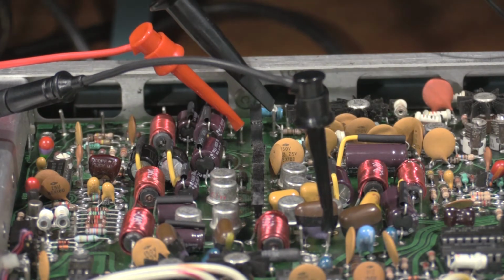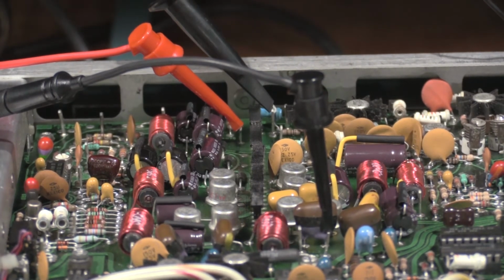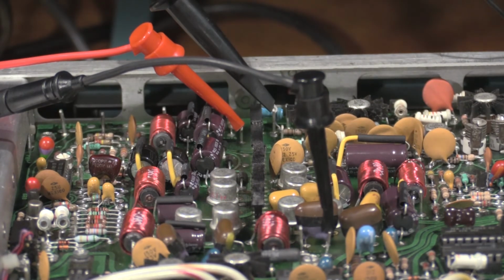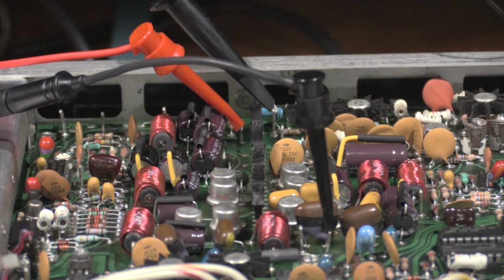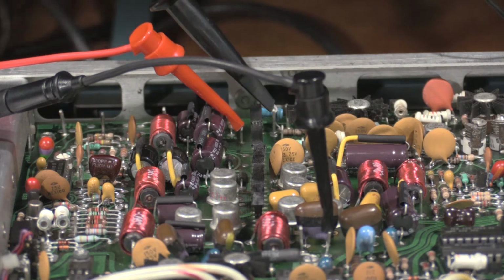And I need to take note of what the autofocus gain is, which is 162.77 volts. Now I need to increase this to a 50 volt step. This is on the test oscilloscope. All right. And that went down to 140.23.